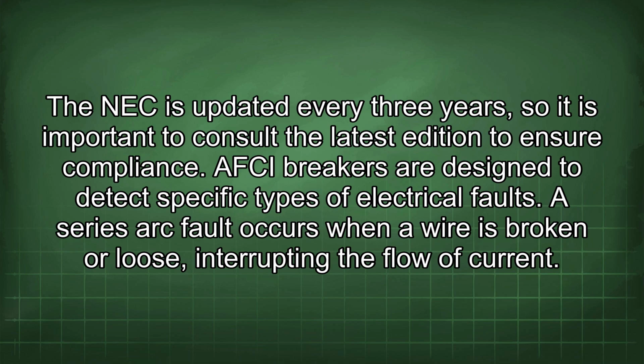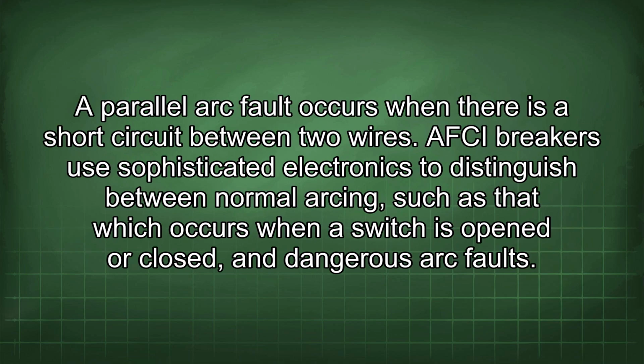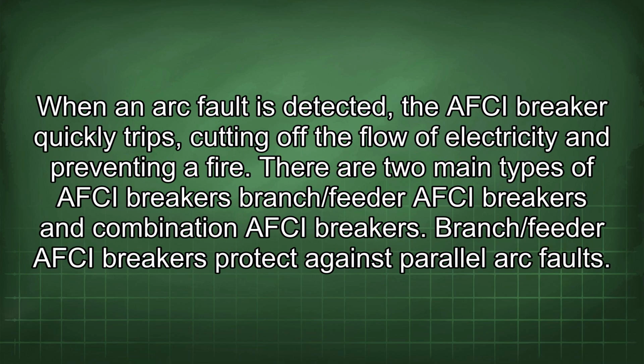AFCI breakers are designed to detect specific types of electrical faults. A series arc fault occurs when a wire is broken or loose, interrupting the flow of current. A parallel arc fault occurs when there is a short circuit between two wires. AFCI breakers use sophisticated electronics to distinguish between normal arcing, such as that which occurs when a switch is opened or closed, and dangerous arc faults.